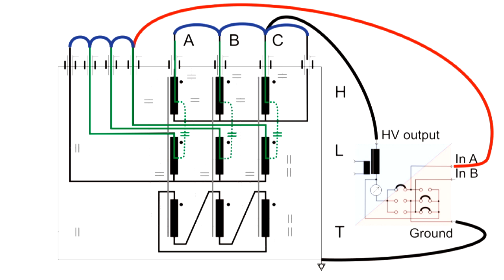Now let's see what happens if we remove this connection. A capacitive current flows through the high voltage winding and the low voltage winding. If the connectors of the high voltage bushings and the low voltage bushings are not connected to each other, current also flows through a second winding.